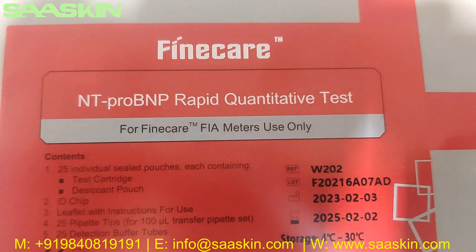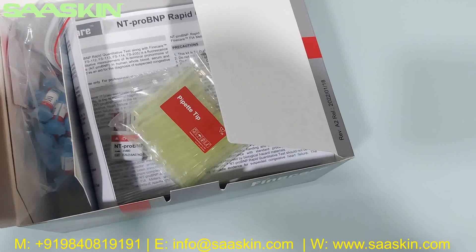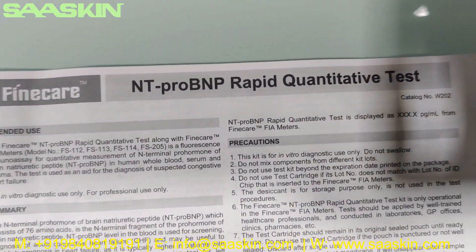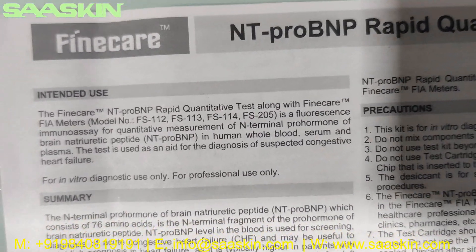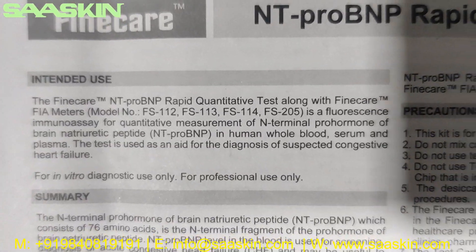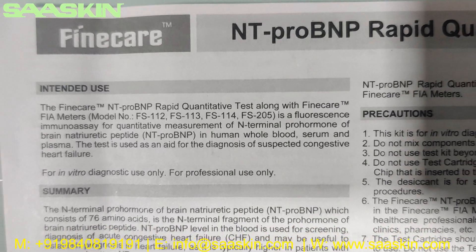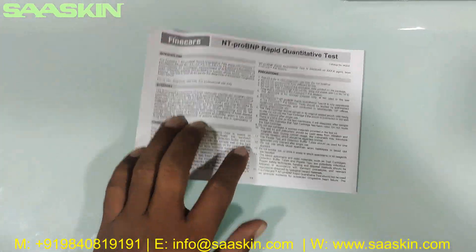This is the Finecare NT Pro BNP Rapid Quantitative Test. I'm going to unbox this for you. Here's the manual — it talks about the Finecare NT Pro BNP Rapid Quantitative Test along with the Finecare FIA Meters. It's a fluorescence immunoassay for quantitative measurement of N-terminal pro hormone of brain natriuretic peptide in human whole blood, serum, and plasma. This instruction manual covers the basic test preparation procedure, test conducting procedure, how to interpret results, how to collect specimens, and the complete test procedure.